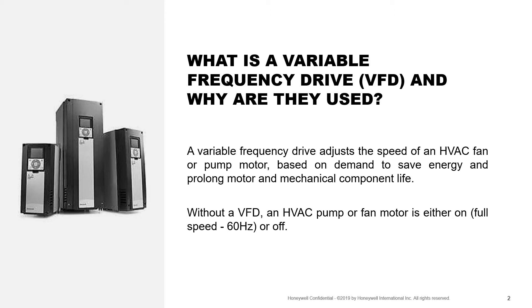A variable frequency drive adjusts the speed of an HVAC fan or pump motor based on demand to save energy and prolong motor life. Heating and cooling systems are sized to condition buildings for when the load is at its greatest — mid-summer for cooling or mid-winter for heating. So what happens during those in-between months? The motor usually doesn't have to run at full speed. A VFD will modulate the fan or pump motor to match the current conditions. Without the VFD, the motor would run at full speed.